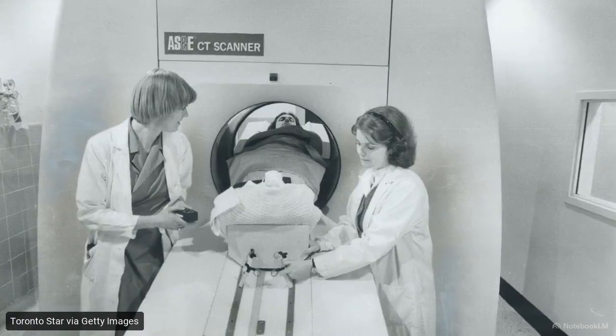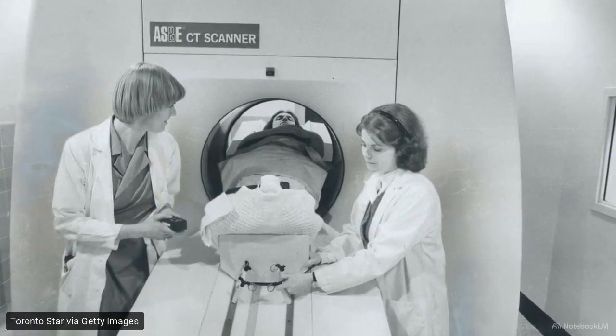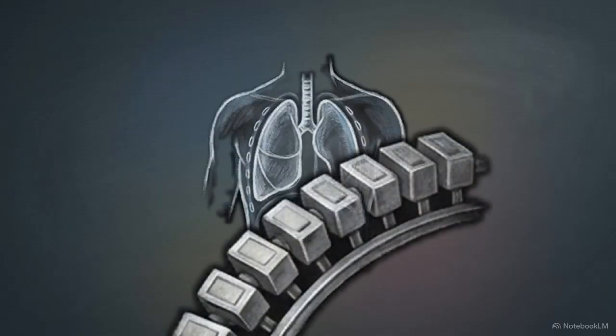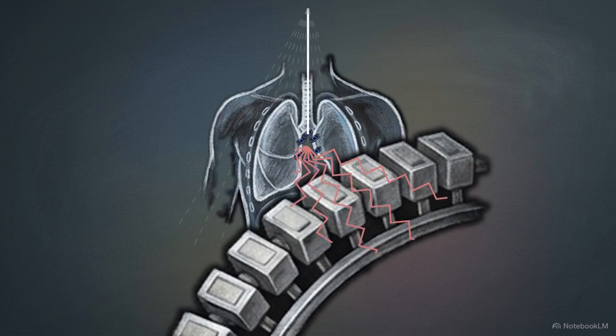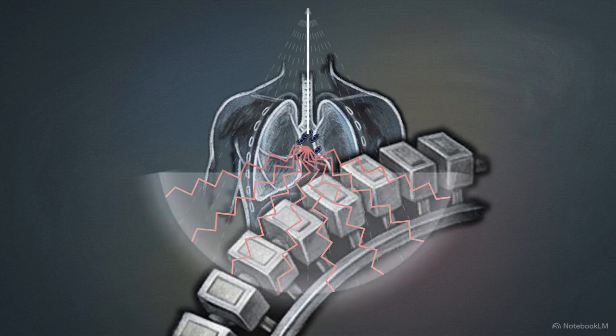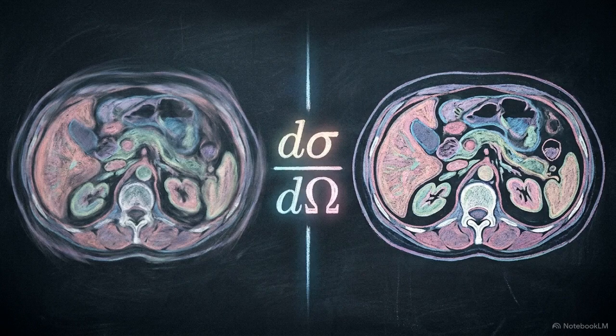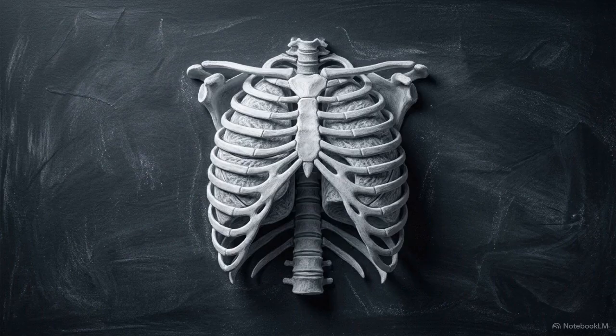Diagnostic CT systems generally operate at X-ray energies around 100 keV. Because this is significantly lower than the electron rest energy, photons possess a high probability of wide-angle scattering within the patient's body. These scattered photons arrive at the detector from incorrect angles, violating the straight-line paths assumed during reconstruction and causing image fog. Modern CT software uses the Klein-Nishina cross-sections to mathematically model and correct for this scatter, preserving the quantitative accuracy of the scan. A clear diagnostic CT image relies on this mathematical filtration of quantum probabilities.